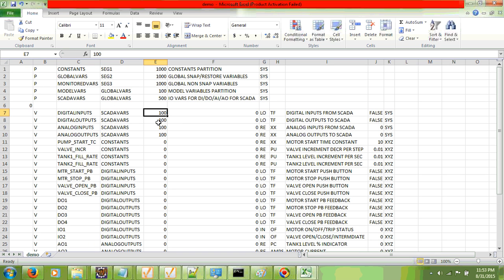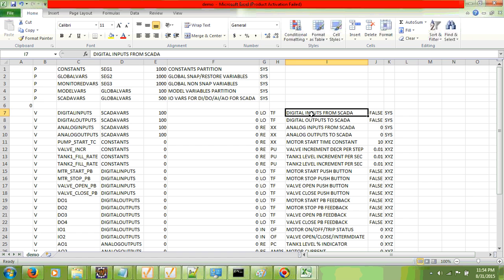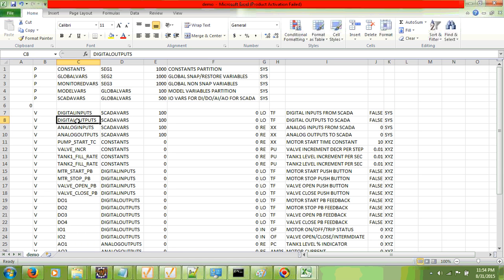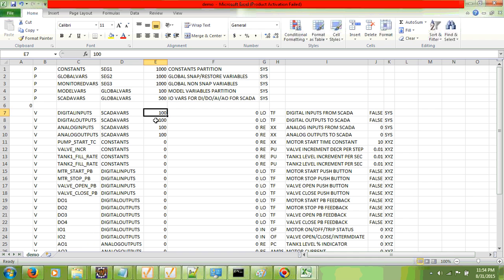After the partitions are defined we define individual variables. Here is a variable which is actually an array added to the SCADA vars partition. It has a size of 100, its type is logical, its units are true/false, with a definition, initial value, and owner. These four array variables are defined in the database under SCADA vars — this maps with the Ignition database we just saw — and each array is given 100 words, all fitting under the SCADA vars partition.